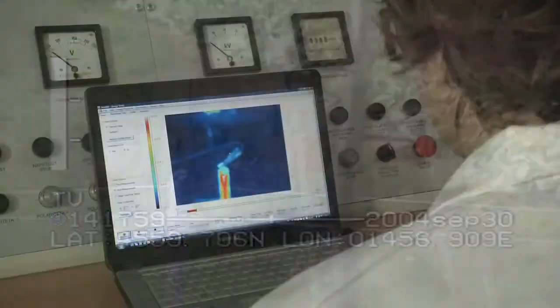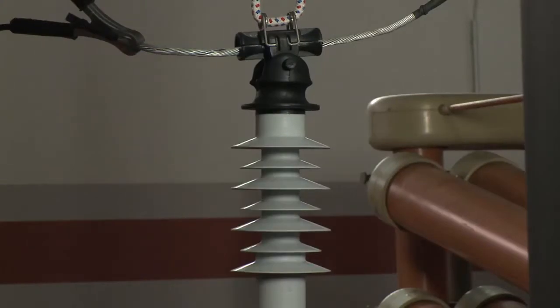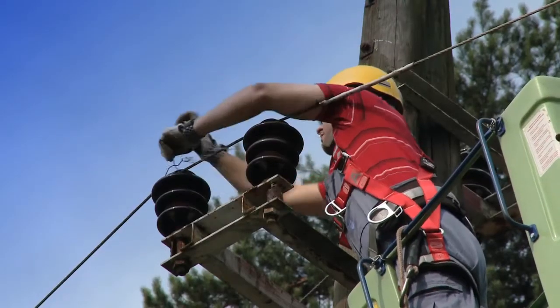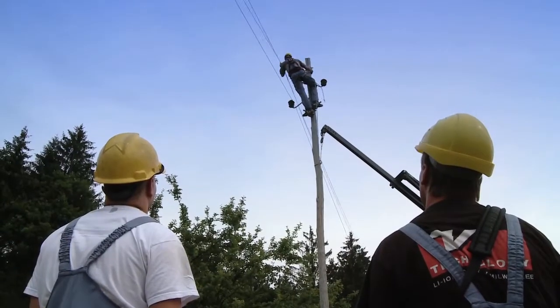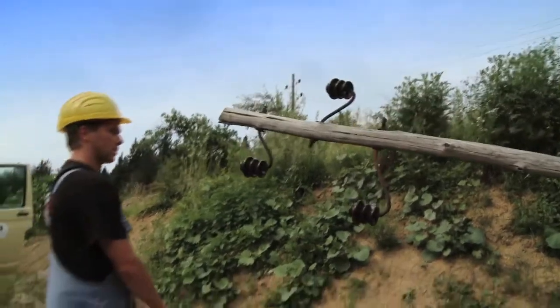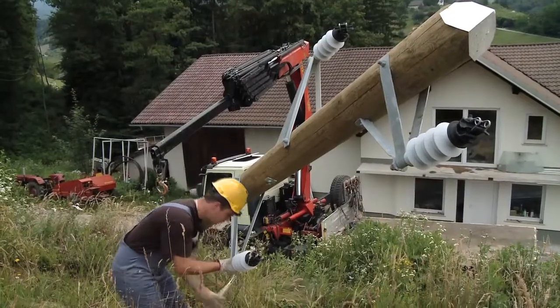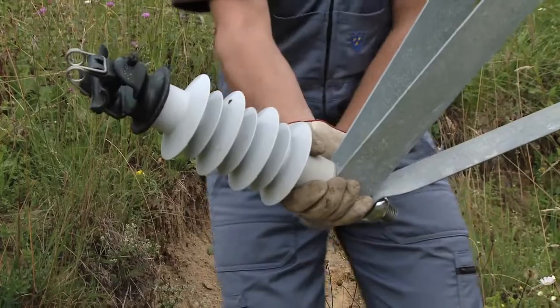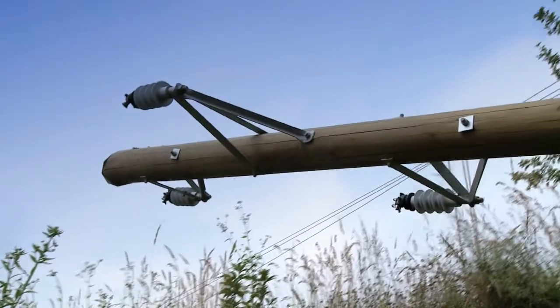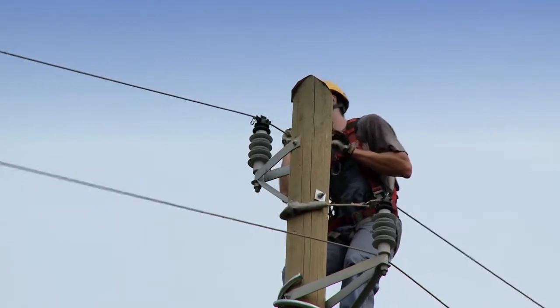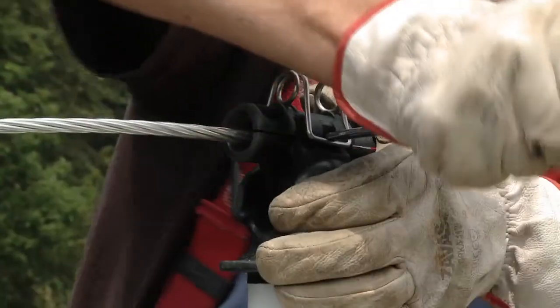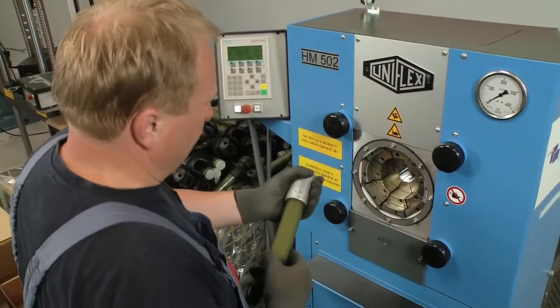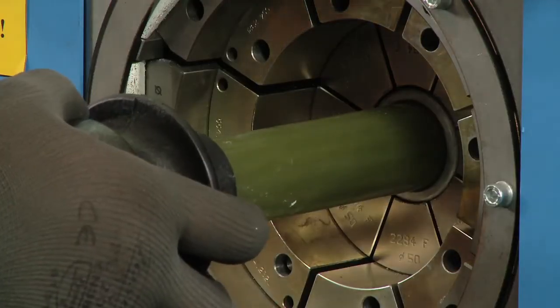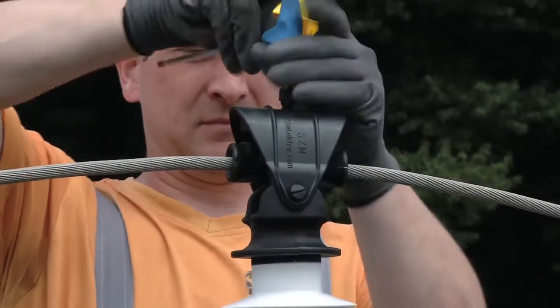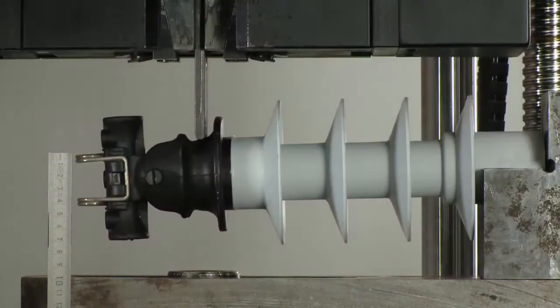Various studies, lab research, and measurements performed on power lines have demonstrated that excessive electric field strength and the resulting partial discharges are likely to occur at a conductor's fastening point onto an insulator with metal end fittings. This may lead to the conductor burning off from its place of fixation after long-term use. Izoelektro Limited solved this problem by developing, patenting, and pioneer manufacturing post-line composite insulators with insulating top-end fittings and an insulating spring clamp. In order to improve its mechanic qualities and usability, we upgraded the insulator's top-end fitting with a protective cap, which enables a 100% increase of insulator load in both horizontal and vertical directions.